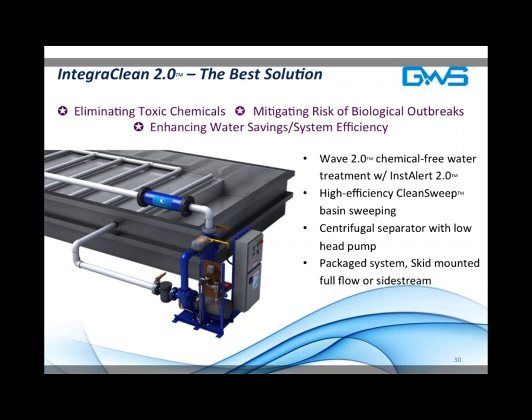Go ahead, Carol. What was the second question on biological? Yes. There's a question: does this system completely eliminate the need to add biocide to the cooling tower water? And what does it measure to ensure that the bacteria levels are eliminated? Great question. As you know, bacteria is measured in a cooling tower through multiple types of tests. One of the most common is an HPC, heterotrophic plate count, which is to say they take a sample of the water, incubate it in a lab, and then count the number of colony-forming units under a microscope.